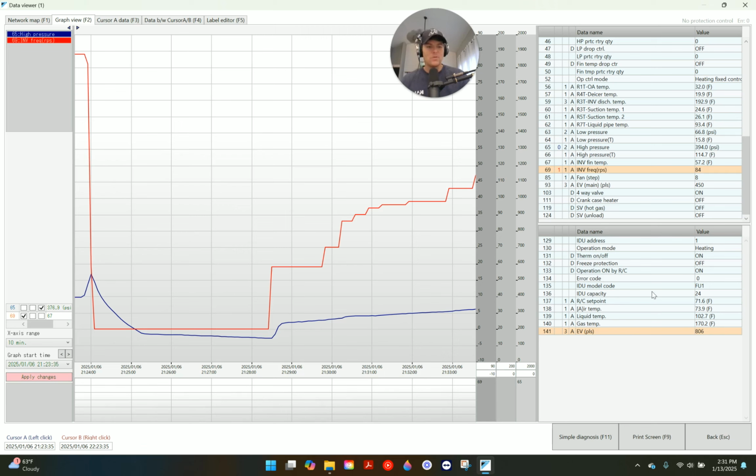Okay, then the next thing, what I also like to look at is my indoor expansion valve. What am I looking at there? How is it operating? Remember, we're in heating mode, so I need to follow this path of flow. I'm going from my compressor discharge over to my heat exchanger, and that heat exchanger isn't outside, it's inside. So I need to follow that path of flow. Now we have the compressor speeds, we know how fast it's running. We have the head pressure, which is the direct thing that's causing the trip, or at least it's seeming to cause the trip.